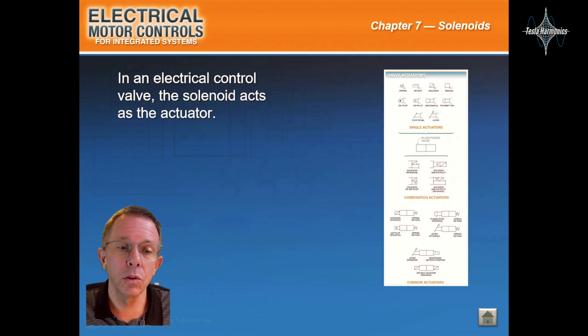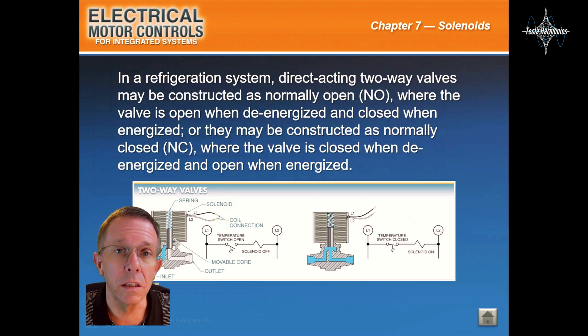In an electrical control valve, the solenoid acts as the actuator. In a refrigeration system, direct acting two-way valves may be constructed as normally open, where the valve is open when de-energized and closed when energized, or they may be constructed as normally closed, where the valve is closed when de-energized and open when energized.